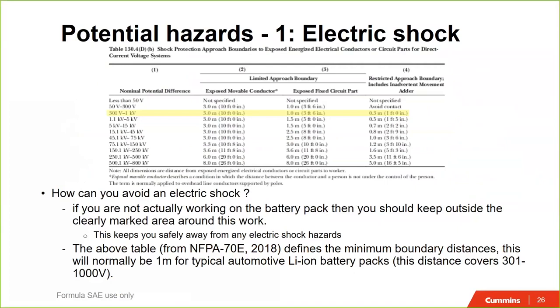One thing of note is the NFPA 70E defines a minimum approach boundary distance for a given voltage. We generally work at the 300 volt to 1 kilovolt range, which dictates an approach boundary of at least 1 meter, or 3 foot 6 inches. So consider getting straps and Tensabarriers so you can keep people away when doing exposed electrical work.